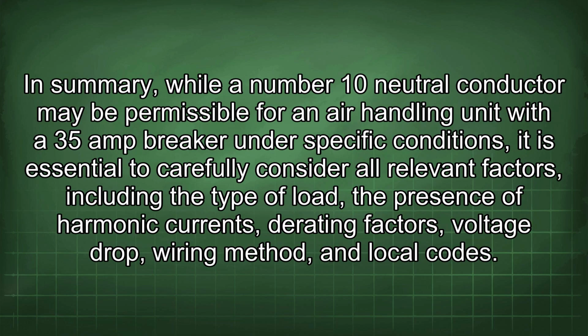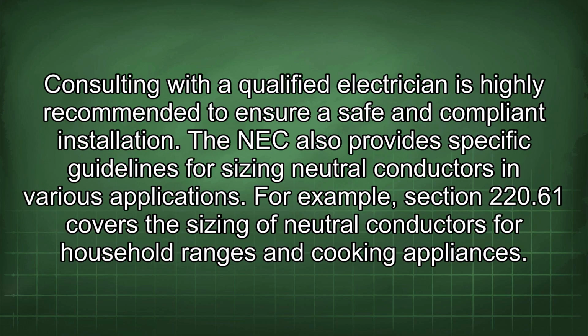In summary, while a number 10 neutral conductor may be permissible for an air handling unit with a 35 amp breaker under specific conditions, it is essential to carefully consider all relevant factors, including the type of load, the presence of harmonic currents, derating factors, voltage drop, wiring method, and local codes. Consulting with a qualified electrician is highly recommended to ensure a safe and compliant installation.